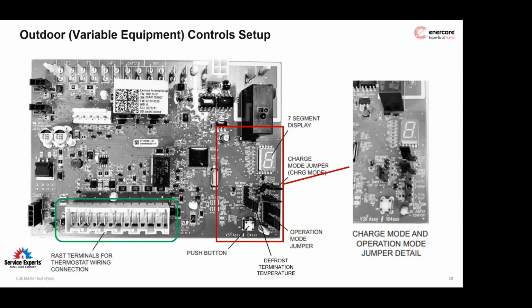Where am I here? On the bottom right of the control is a series of jumpers. You can see highlighted in red there, and in the blown up version, one is highlighted in blue. One is for defrost termination temperature. We've talked about this previously in other Lennox-based trainings. Lennox has suggested a minimum of 70 degrees defrost termination temperature. I'm going to suggest to you up to 90 as well.